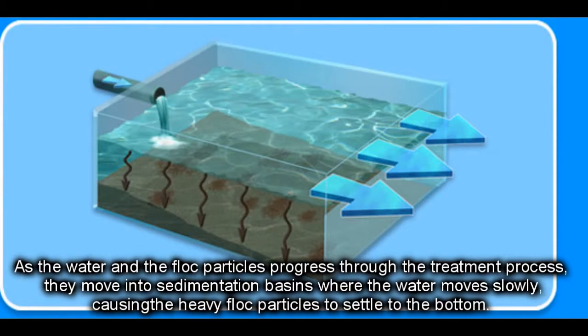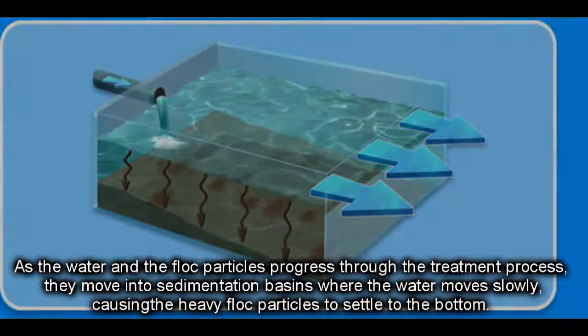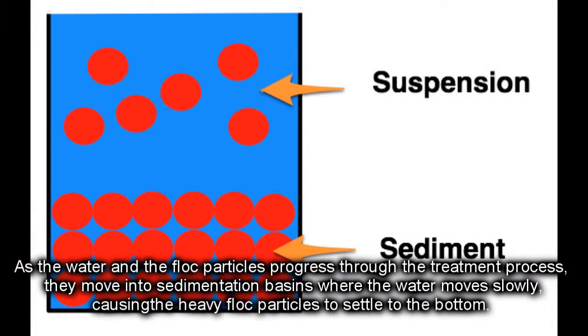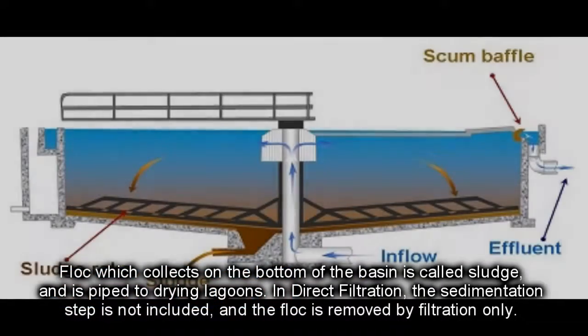Sedimentation. As the water and the floc particles progress through the treatment process, they move into sedimentation basins where the water moves slowly, causing the heavy floc particles to settle to the bottom. Floc which collects on the bottom of the basin is called sludge and is piped to drying lagoons. In direct filtration, the sedimentation step is not included, and the floc is removed by filtration only.